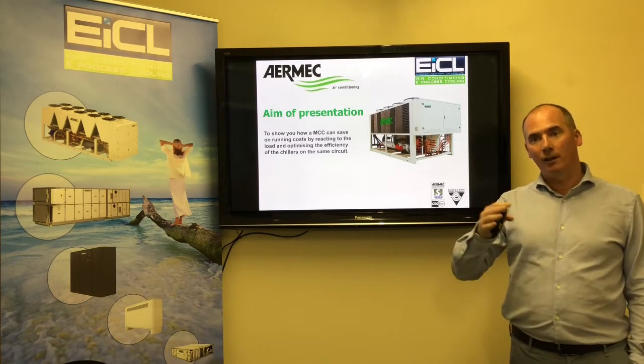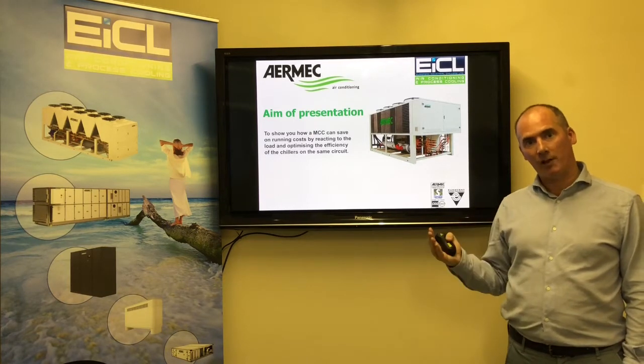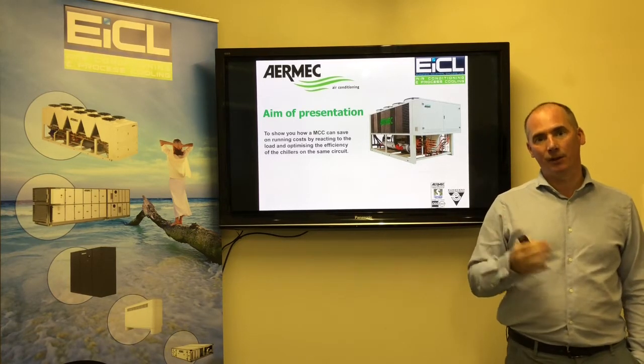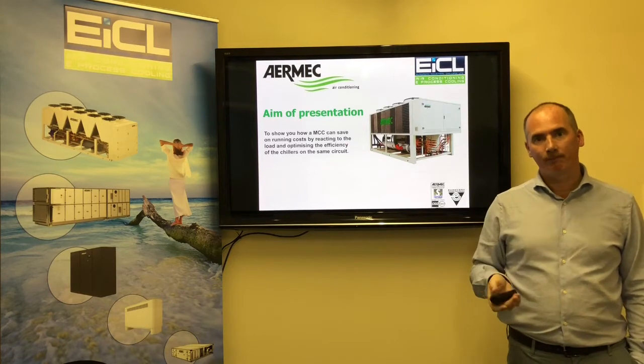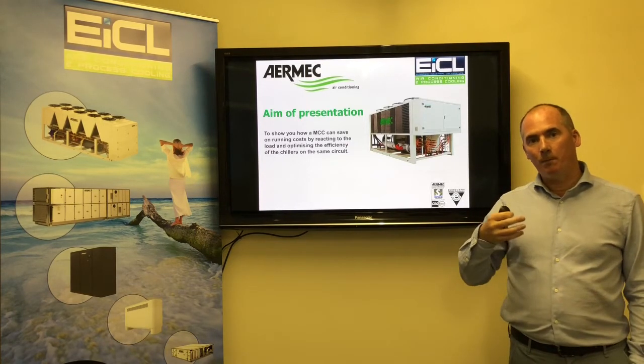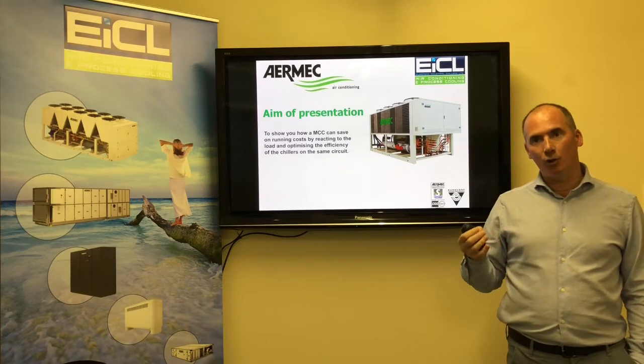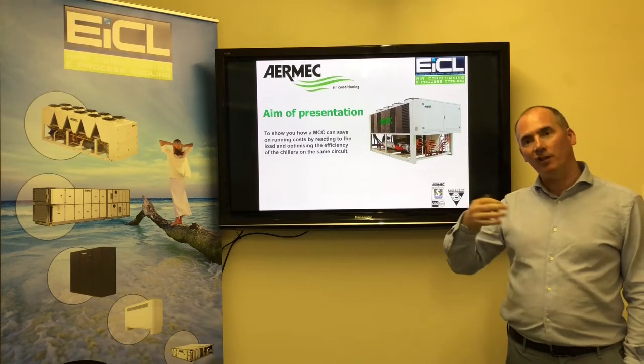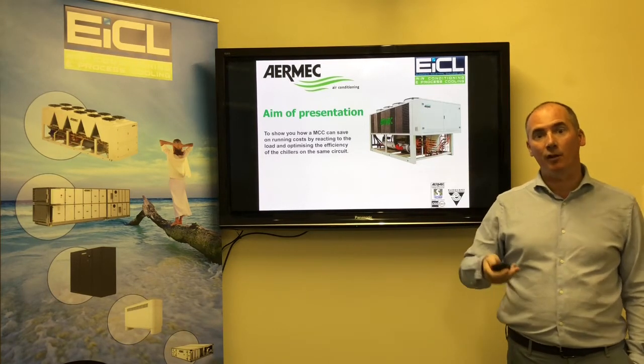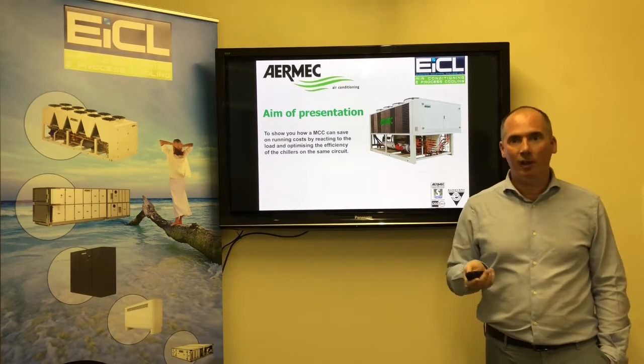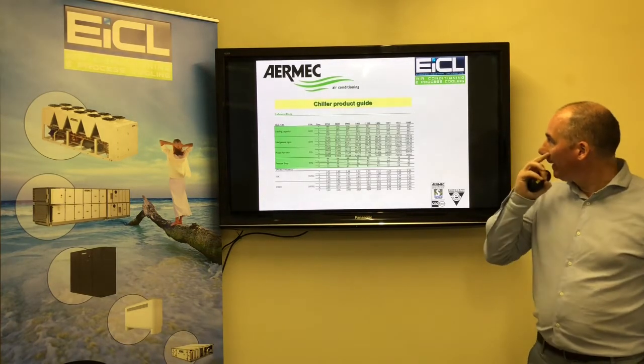If you run the vast majority of chillers up to 100% load, they're running at their least efficient mode of operation. So if we pay consideration to the part load efficiencies, you can see how we can dramatically improve the efficiency of a system. So that's what this is all about, so I'll crack on.